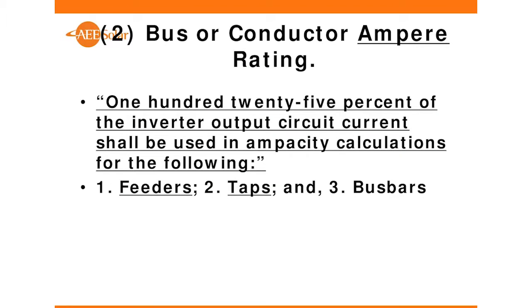Okay, when we get into busbar or conductor ampere rating, the previous versions of the code use the circuit breaker rating for all the calculations. Unfortunately, with using the circuit breaker rating, that can create some problems, particularly for microinverters, more than probably anything else, whereby it's pretty common, for those of you who are familiar with doing microinverter systems, to have, let's say the maximum number of microinverters you can put on a 20-amp circuit breaker is 15. All right?